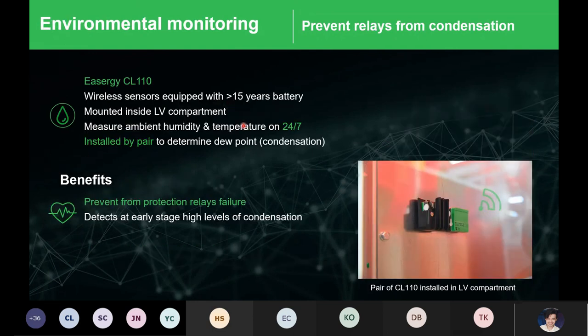Now, apart from this, we also have other sensors to identify the possibility of humidity, because it will cause moisture. So this whole process is to prevent condensation. These sensors also will be self-powered, and it's 24/7 as well. Okay, sorry, this one actually has a battery inside, not self-powered, I said it wrongly. But the battery has a long lifespan, about 10 to 15 years.